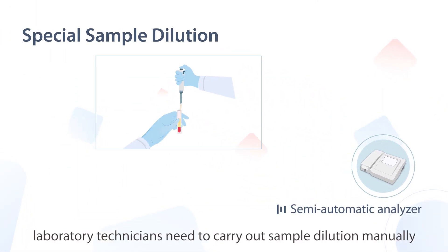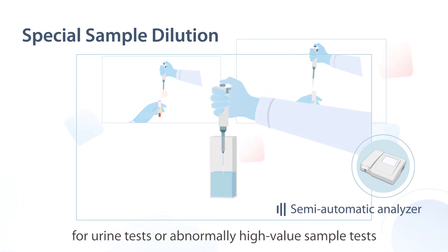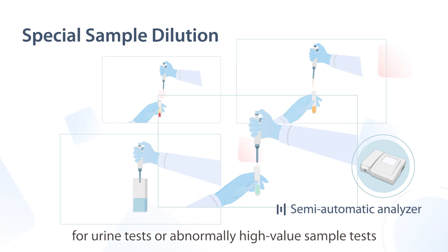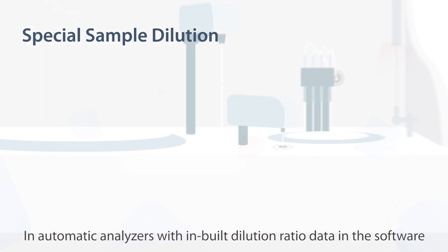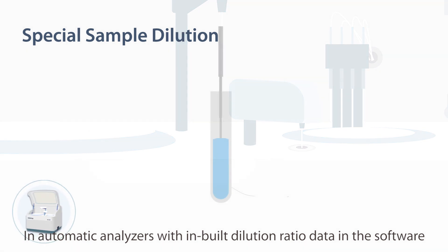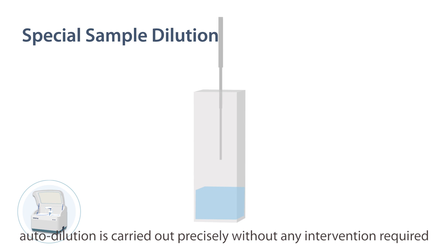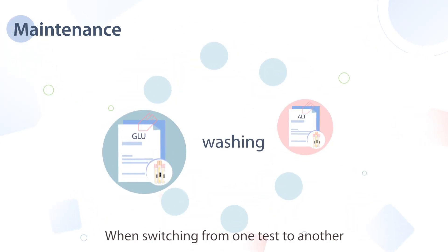With semi-automatic analyzers, laboratory technicians need to carry out sample dilution manually for urine tests or abnormally high-value sample tests. In automatic analyzers, with inbuilt dilution ratio data in the software, autodilution is carried out precisely without any intervention required.